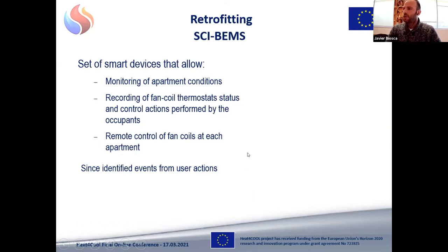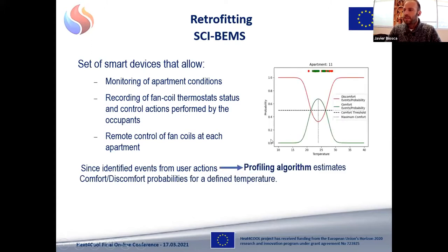Finally, the retrofitting also comprises the implementation of the SCI BEMS. This is a set of smart devices that allow the monitoring of apartment conditions, the recording of fan coil thermostat status, and the control actions performed by the occupants, and also the remote control of fan coils at its apartment. Then, since the identified events from user actions, the profiling algorithm of the SCI BEMS estimates the comfort-discomfort probabilities for a defined temperature, as we can see in this graph of the picture.